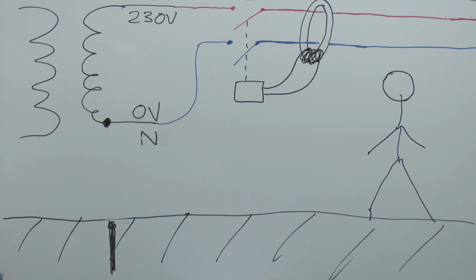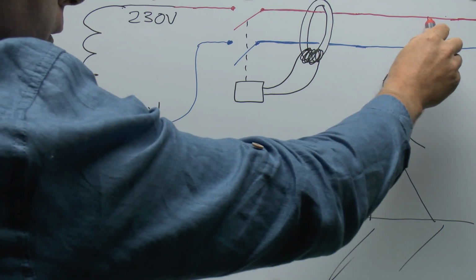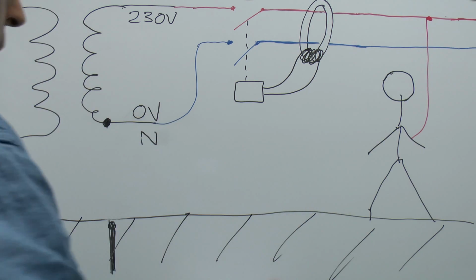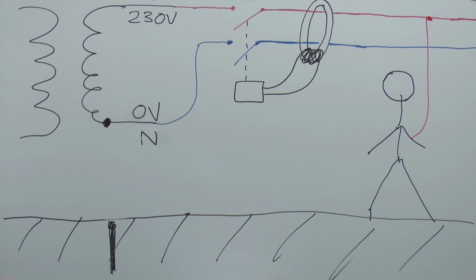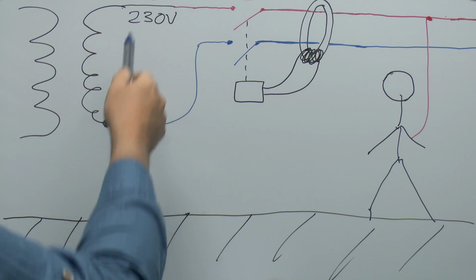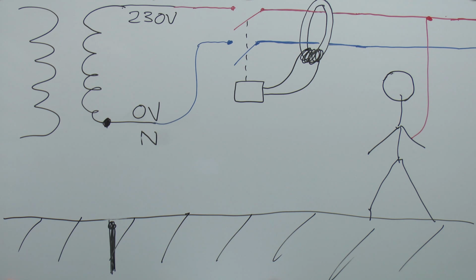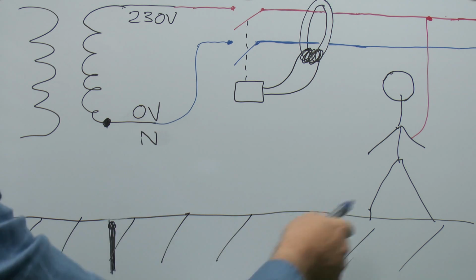of course is a self-contained device, and although it generates the 230 volts as supply, that may or may not be referenced to ground. So of course if it wasn't referenced to ground, somebody, say touching the wire here, isn't actually going to trip any kind of RCD, simply for the fact that there's no return path for the current. So voltage supply here, the person's touching it, so they would be at the same potential as the terminal here on the generator, but nothing will actually happen because of course there's no return path for the current back here. This also means that the person wouldn't actually get an electric shock in these circumstances, simply because again there's no return path for the current.